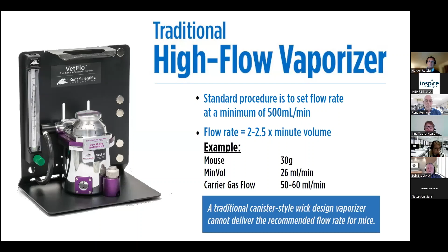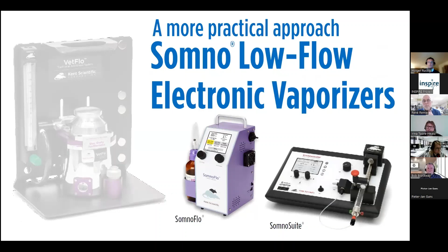So about 10 years ago, we came up with this concept of a low flow electronic vaporizer. The one you see on the right hand side is called the SomnoSuite, and about 2 years ago we came up with the one you see on the left hand side called the SomnoFlo. The concept of these was to deliver exactly what the animal needs. The SomnoFlo anesthesia system delivers based on the weight. It uses room air versus compressed gas. It does not require calibration because it is an electronic vaporizer versus the traditional vaporizer.